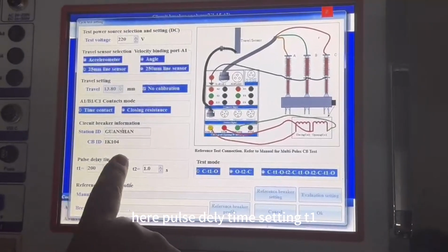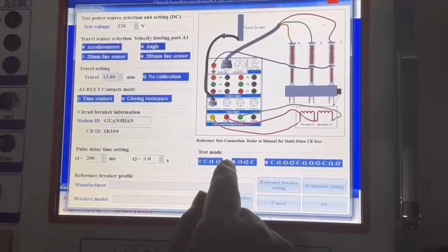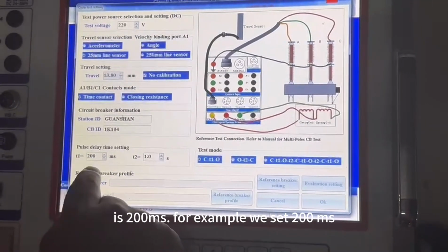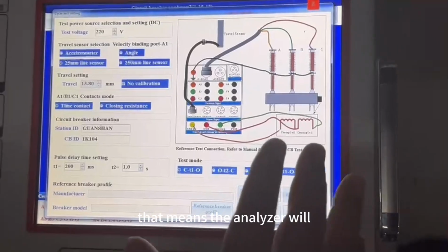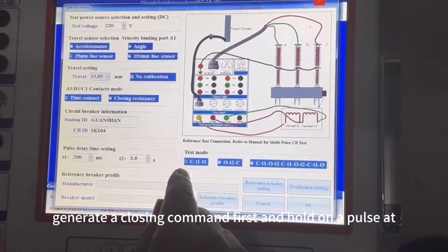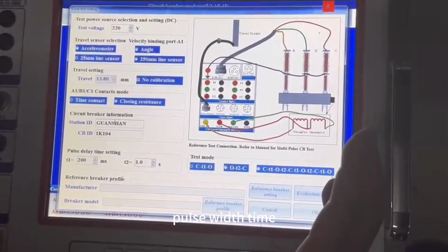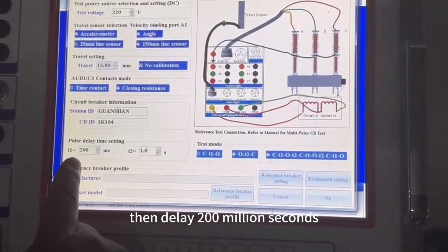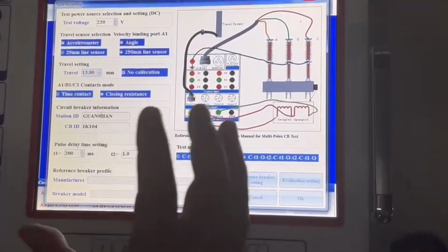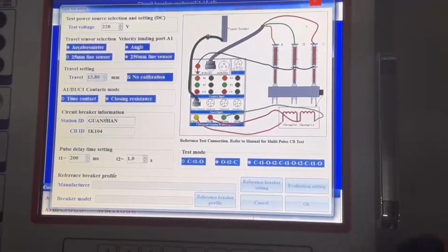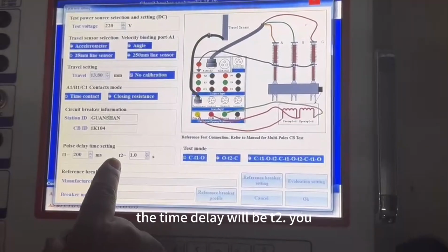Here, pulse delay time setting. T1, we can see here, this is the test mode. If you select the CO, there is a time delay T1. For example, we set 200 milliseconds. That means the analyzer will generate a closing command first and hold on for the pulse width time, then delay 200 milliseconds, then generate another test command, opening, for the pulse width time. If we select the OC test mode, the time delay will be T2.